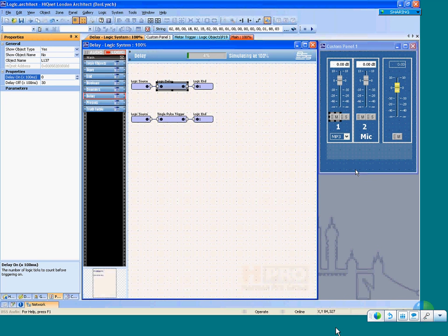Now, realistically, if you're talking about the difference between 3 seconds and 3 seconds plus 18 milliseconds, probably not a big deal. However, if you start trying to use the logic delay to set 9, 10, 12, 20-minute, 30-minute delays, your margin of error gets really unacceptably huge really fast.